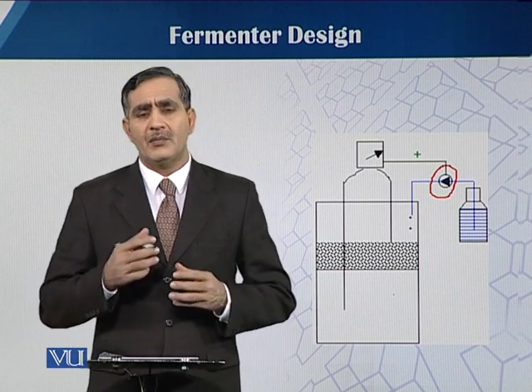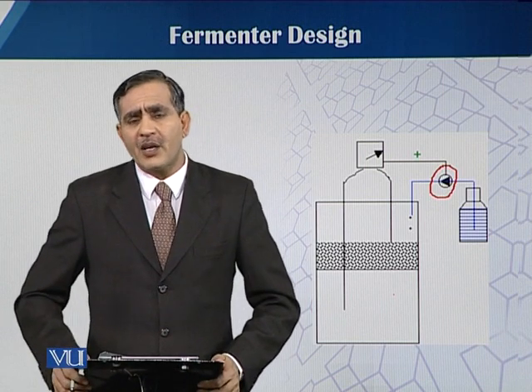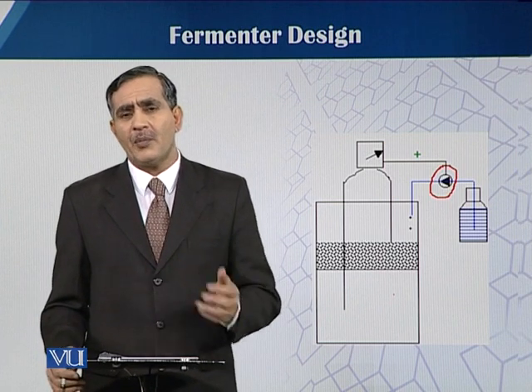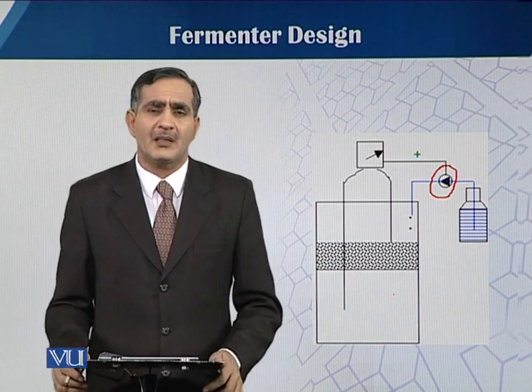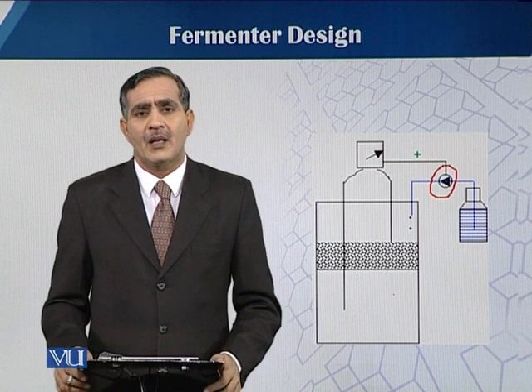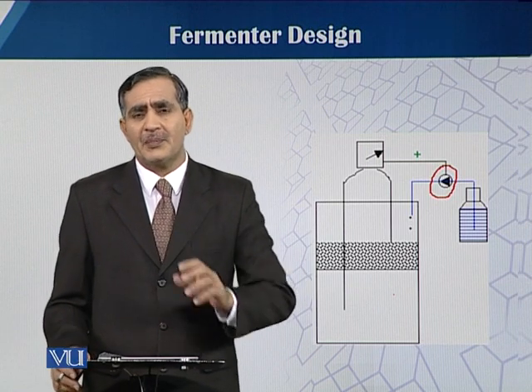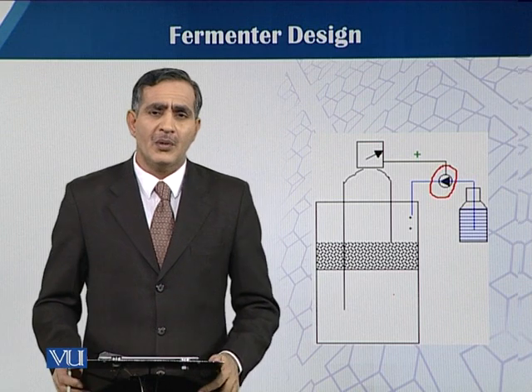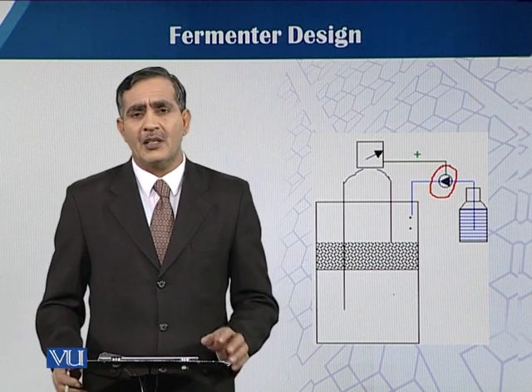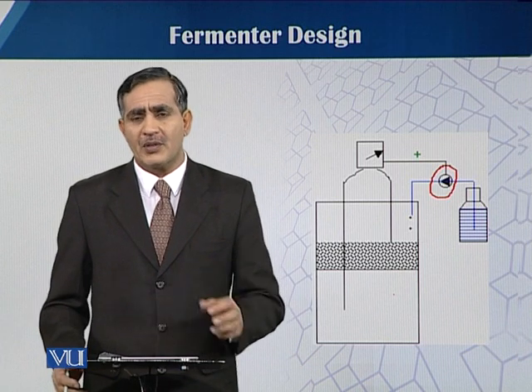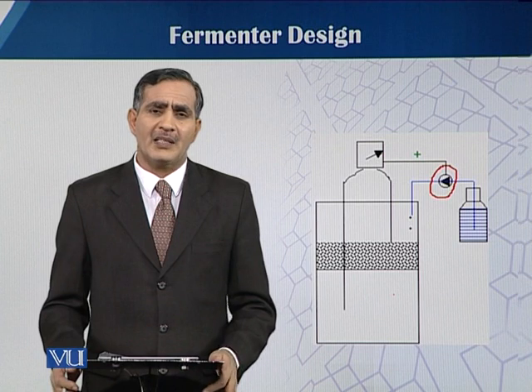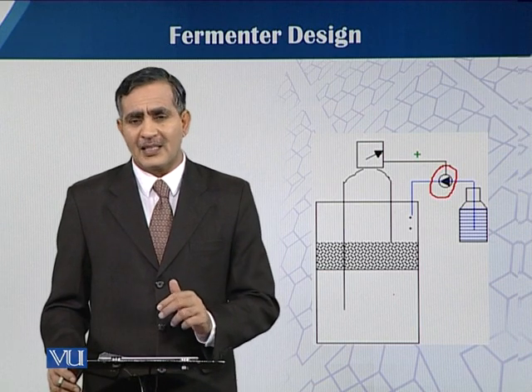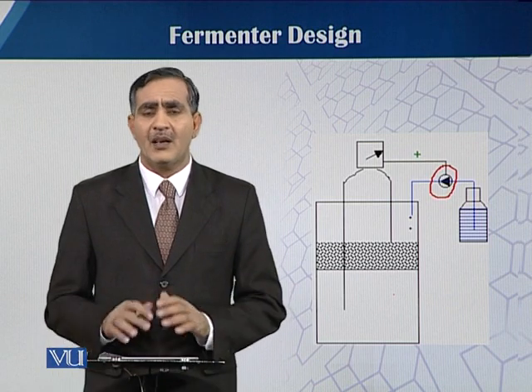However, when using this wet-on and wet-off level probe system, there is a practical problem in fermentation because the whole process is aqueous. Sometimes vapors are produced, and when those vapors touch the upper level probe, they give a false signal to the pump, causing anti-foam addition to continue as a constant process — even when it is not needed.